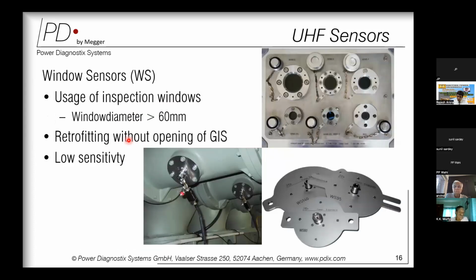There are certain old GIS where you have inspection windows available, like this, which are generally used to see inside the GIS if there are any visible indications of deformation. This window can also be used for connecting a window sensor, which can be retrofitted into this kind of GIS opening without opening the GIS, and can also be used for partial discharge measurement. The only criterion to take care of is that the window diameter should be more than 60 mm. Then only the useful PD radiations can be captured. Otherwise, not all of the partial discharge frequency spectrum will be captured and we will have half the information. Again, this being an external element offers lower sensitivity.